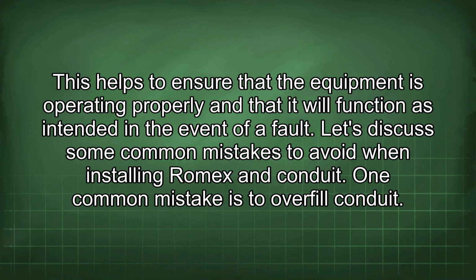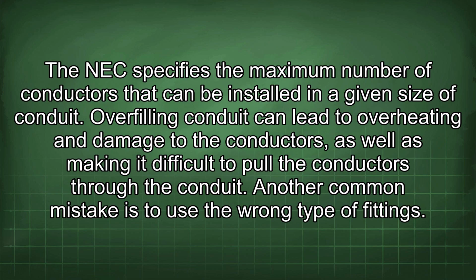One common mistake is to overfill conduit. The NEC specifies the maximum number of conductors that can be installed in a given size of conduit. Overfilling conduit can lead to overheating and damage to the conductors, as well as making it difficult to pull the conductors through the conduit. Another common mistake is to use the wrong type of fittings.